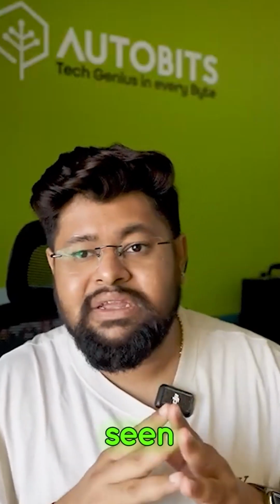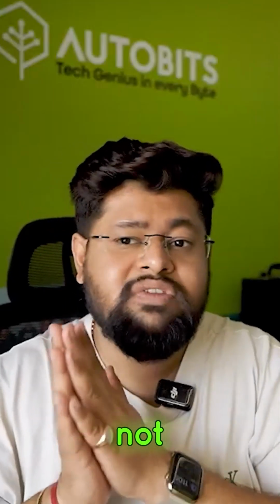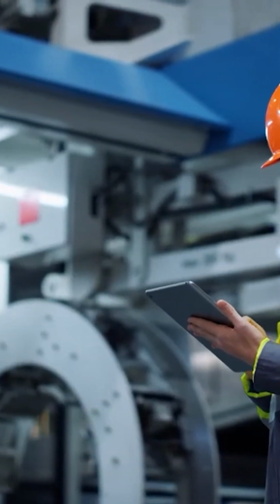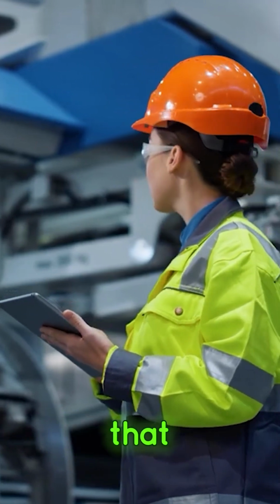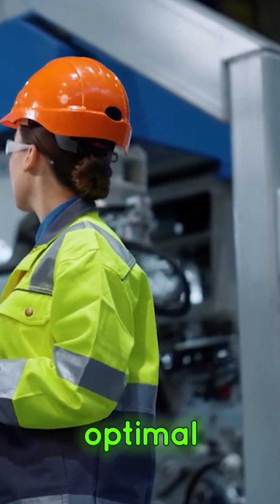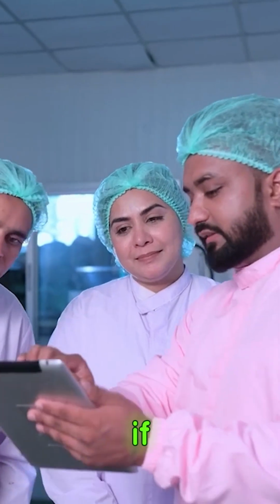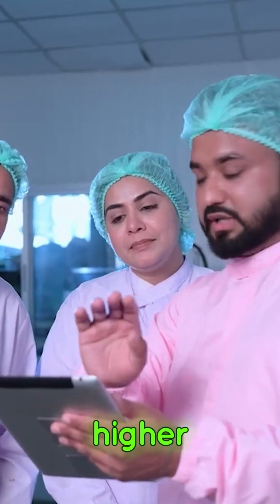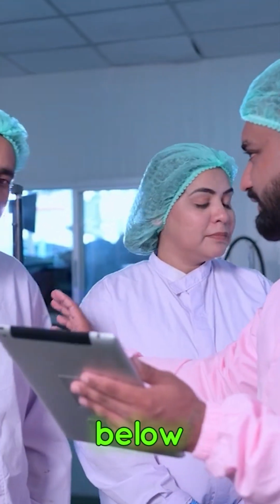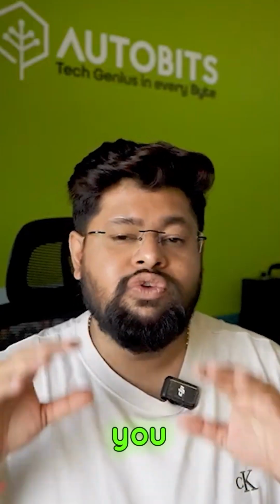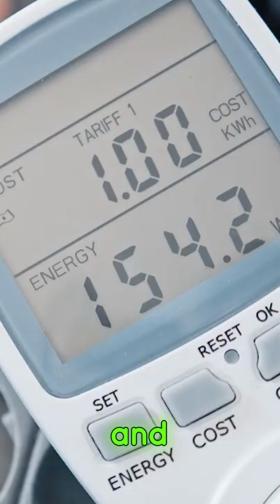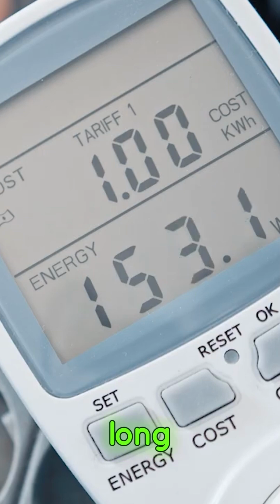Another thing I've seen is that after getting into energy monitoring, people don't set any baseline. Say you've got lots of machines on your shop floor or in the factory, but you haven't set a baseline for when five of your machines are working optimally, and what current they should consume. If they're taking higher current than that, or lower, maybe something is failing, and you'll know. Unless you set a baseline, you won't know what's happening in your factory. Creating that baseline as 100 is very good and will help you a lot in long-term monitoring.